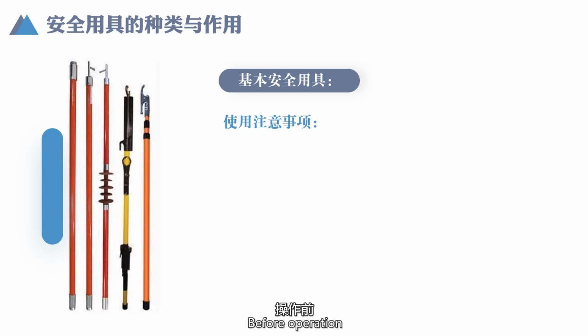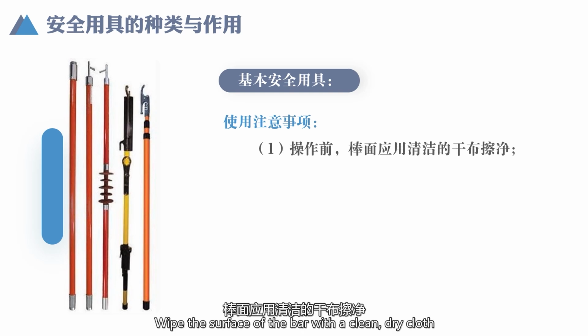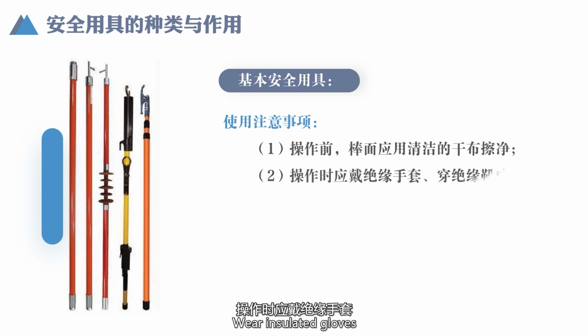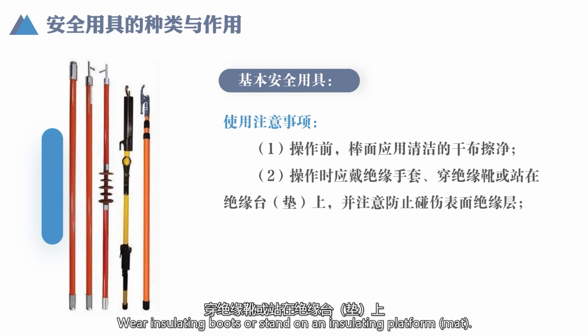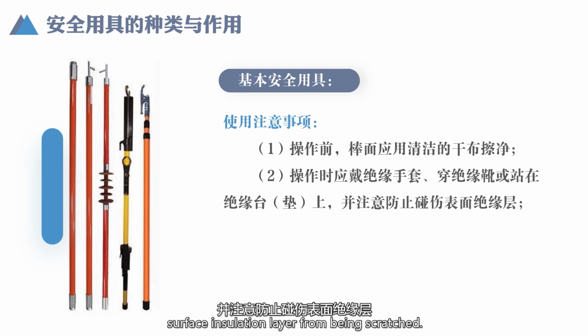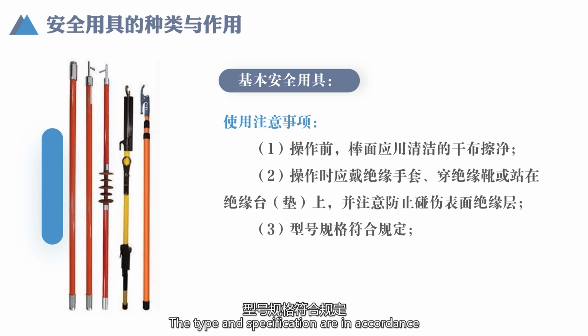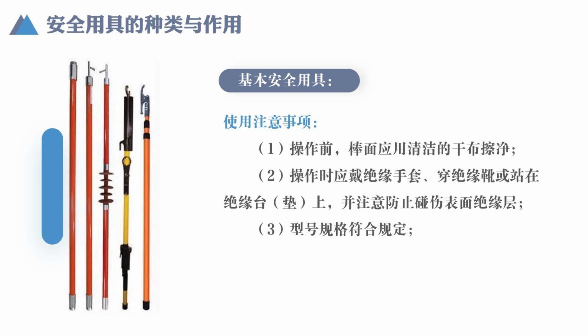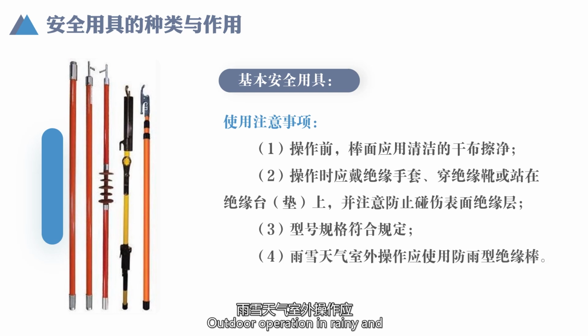Precautions for use. Before operation, wipe the surface of the rod with a clean, dry cloth. Wear insulated gloves. Wear insulating boots or stand on an insulating platform or mat. Be careful to prevent the surface insulation layer from being scratched. The type and specification should be in accordance with the regulations. Outdoor operation in rainy and snowy weather should use a rainproof insulating rod.